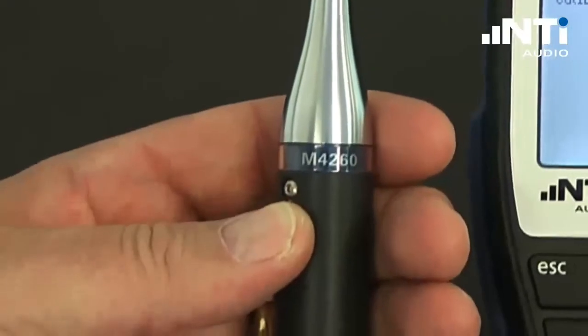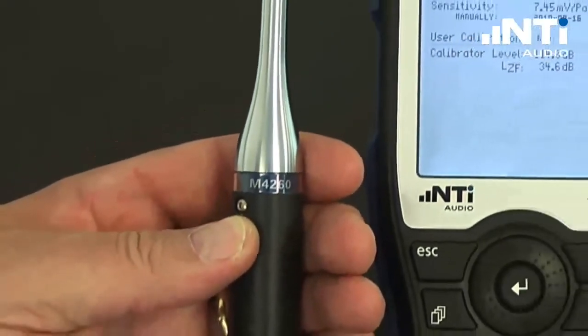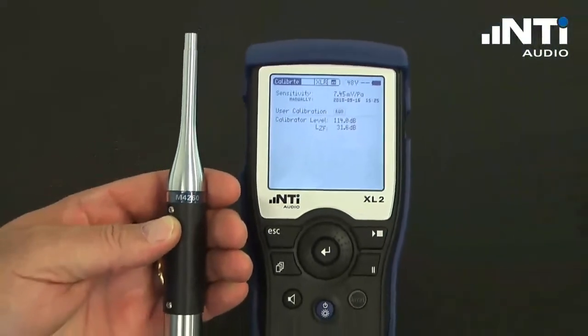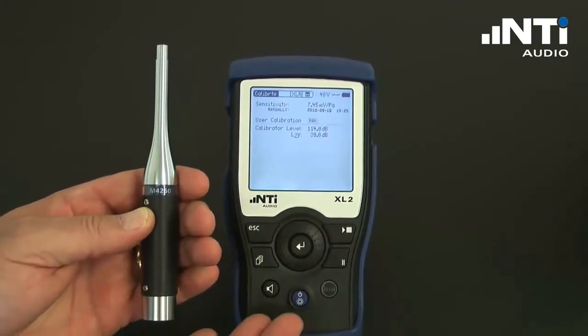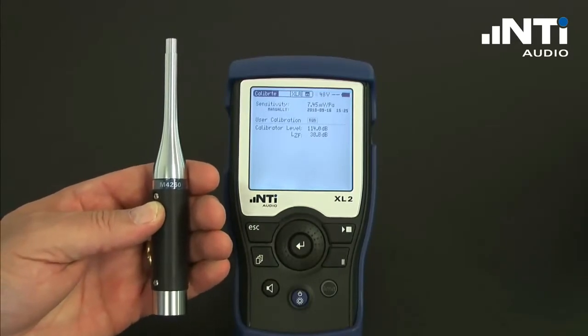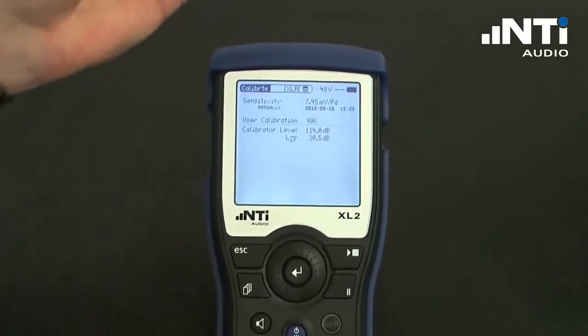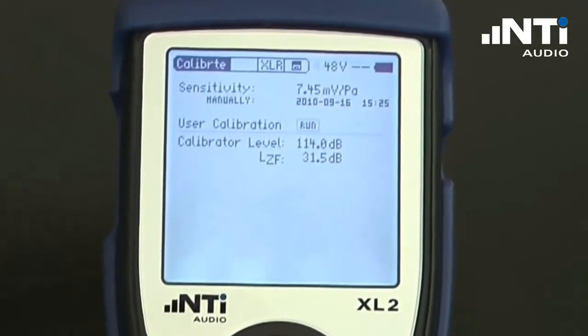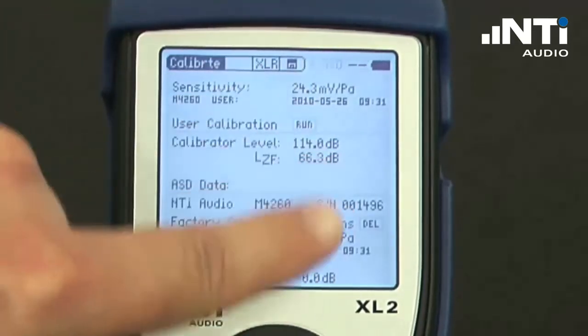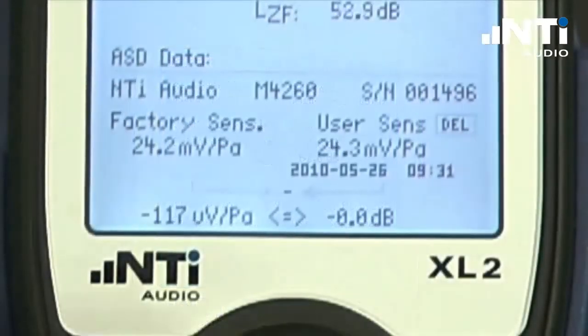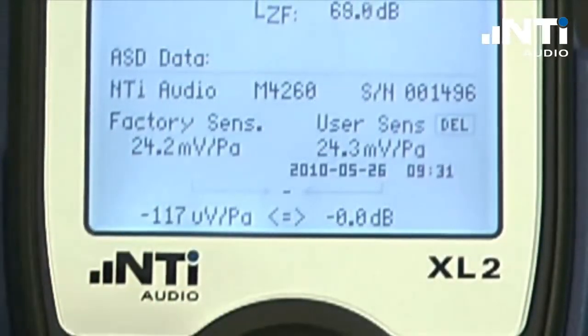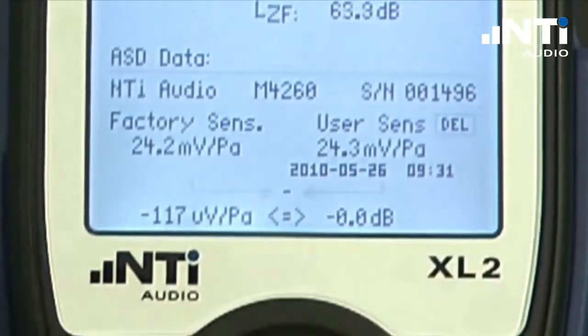The M-Series measurement microphones feature an automatic sensor detector that reads the previously stored calibration data out of the microphone into the measurement instrument. As soon as we connect this microphone, it switches over to ASD and reads all the calibration data out of the measurement microphone, including the factory calibration and the last user calibration together with the measurement date and time.